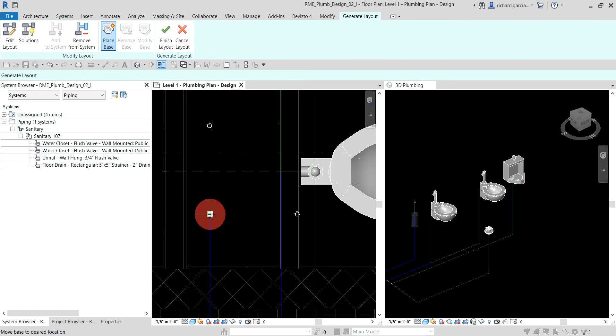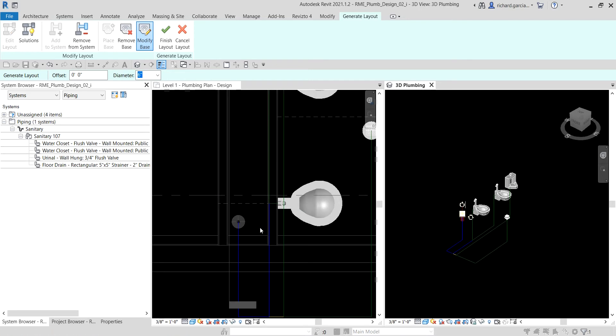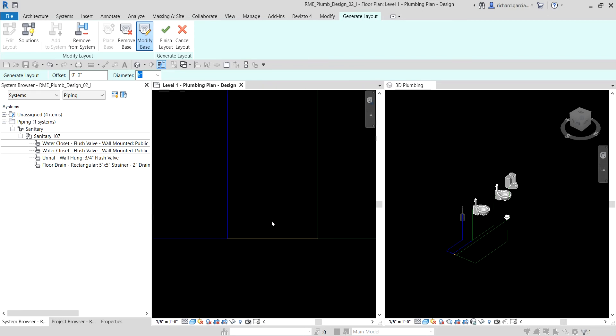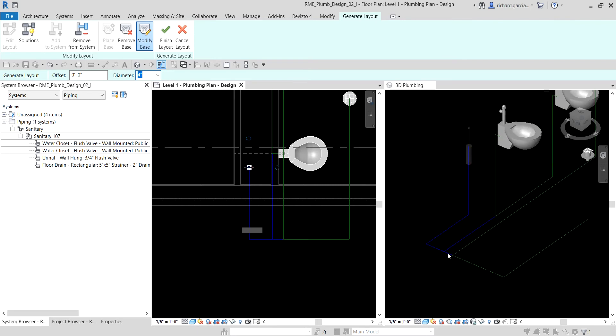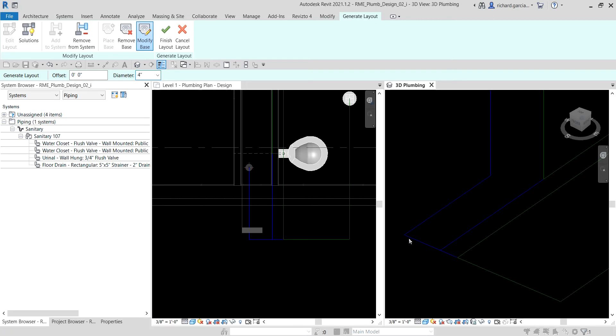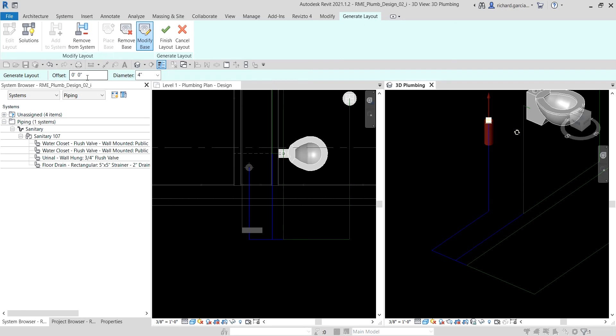I'm going to select Place Base and place it here. You can see a preview in the 3D view as well. You'll notice some orange, meaning there will be a problem, but you can still modify it manually. If I change the diameter to four inches, it will update and the problematic pipe will disappear because we've changed the size of the pipe.